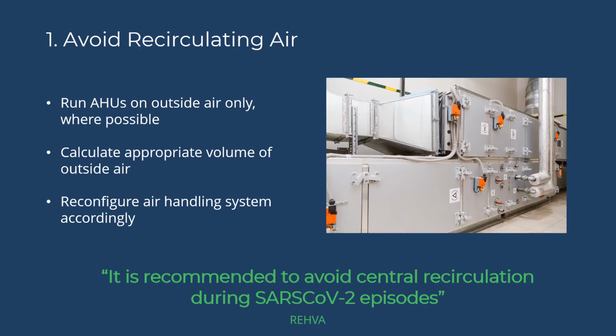The first measure is to avoid recirculating air. The reason for this is that virus particles can re-enter a building through the recirculated air system. Most air handling units have a duct between the exhaust air and the fresh air intake that allows some of the exhaust air to be recirculated back into the system.